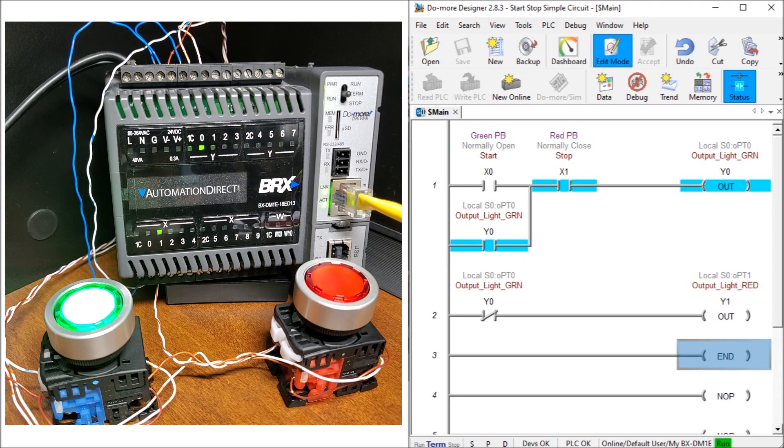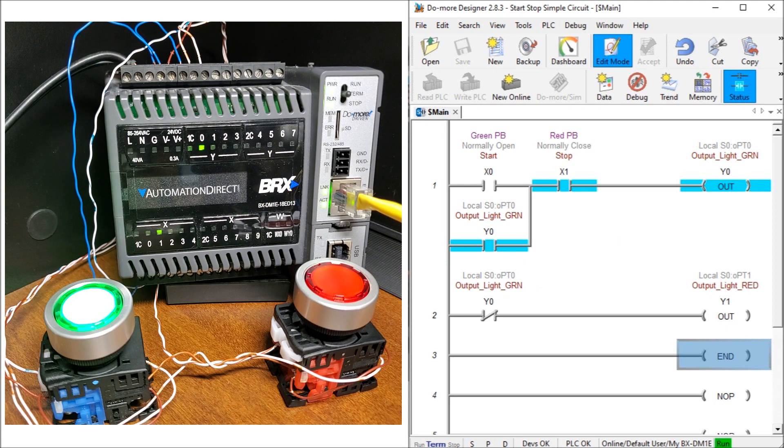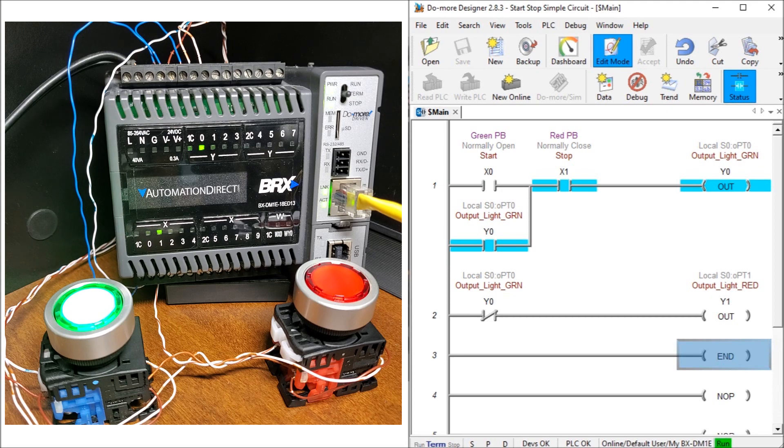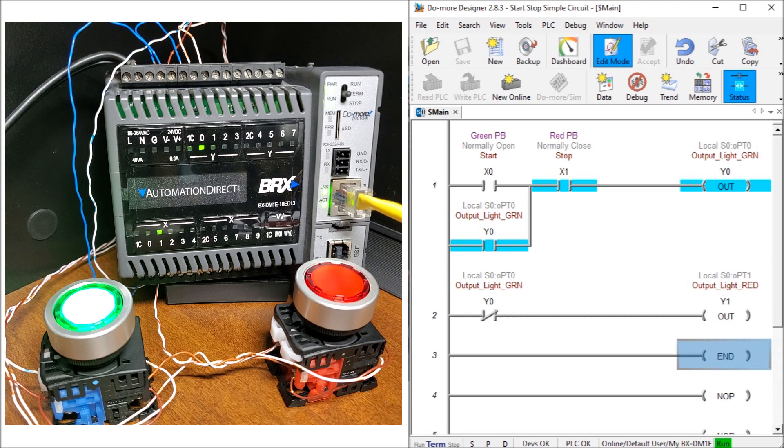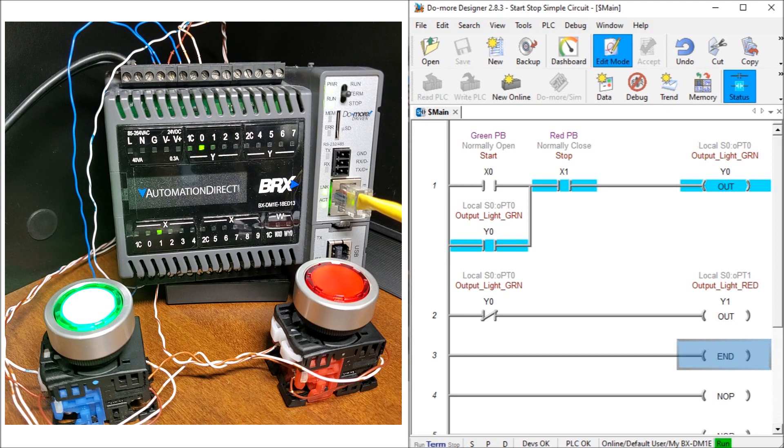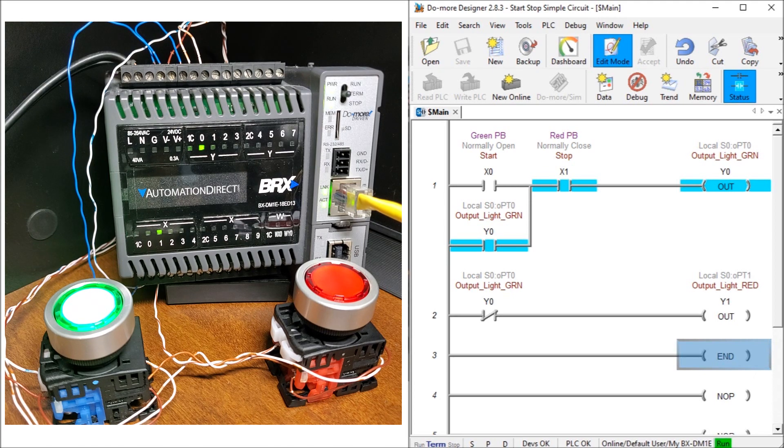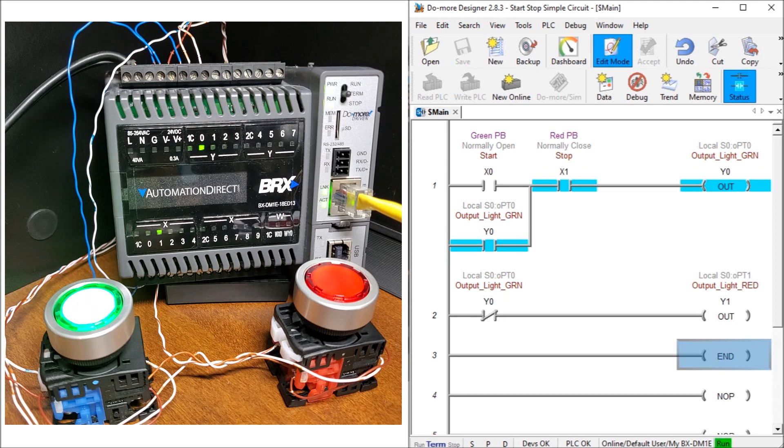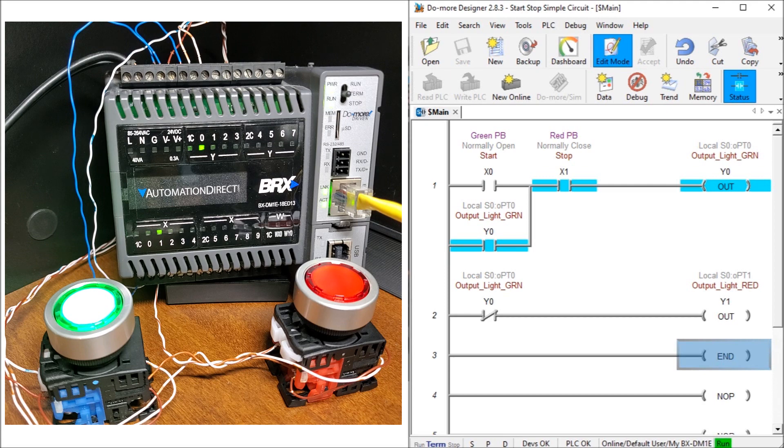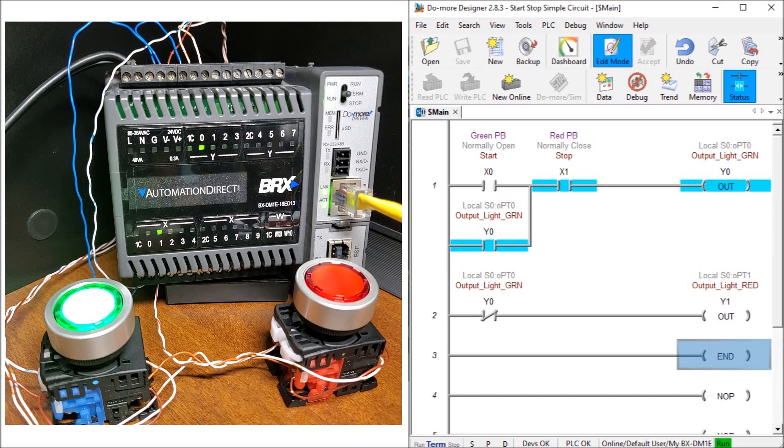The other thing that we can do was online programming or editing of the ladder logic in the PLC. It's now standard with most modern PLCs today. This will allow you to change the ladder logic while the machine is still scanning and solving the logic. Online editing will hold the scan, insert the new code, then release the scan. This happens all within a fraction of the time. Troubleshooting and commissioning of the systems rely on this important feature of the PLC.